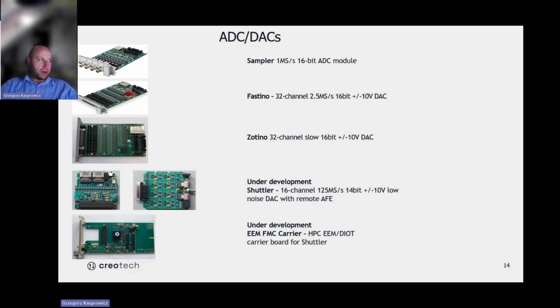And currently under development we have a Shuttler, which is a 16-channel board, but it has a different philosophy. The Fastino generates signals at the source, and then you need to have these long cables which deliver them to the trap. Shuttler is optimized for very low noise operation and for much faster operation. So the front-end module is placed directly at the trap, close to the trap, to limit the capacitances, and that's why we are able to achieve a much higher update rate and much lower noise, because first of all we have fully differential signaling between the DAC and the output amplifier, and also because we keep much lower impedances.